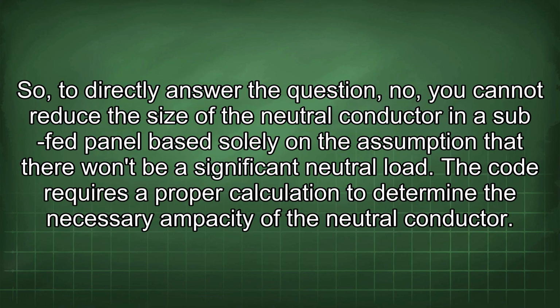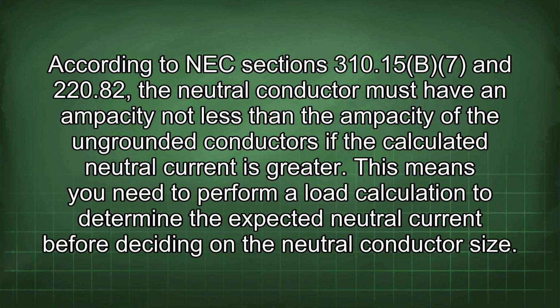load. So, to directly answer the question, no, you cannot reduce the size of the neutral conductor in a subfed panel based solely on the assumption that there won't be a significant neutral load. The code requires a proper calculation to determine the necessary ampacity of the neutral conductor. According to NEC sections 310.15(B)(7) and 220.82, the neutral conductor must have an ampacity not less than the ampacity of the ungrounded conductors if the calculated neutral current is greater.